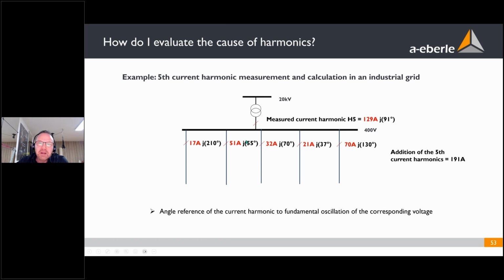the fifth harmonic, the current of the fifth harmonic goes up. So this is a producer of harmonic, but if you switch it off, it gets worse. So with this information, it's much more useful for you to look for solutions. So if we have here on this bus bar a problem with the fifth, I will analyze which frequency converter we change from 6-pulse to 12-pulse converter, because they do not produce a fifth harmonic. But I do this effort only where the fifth harmonic is negative.